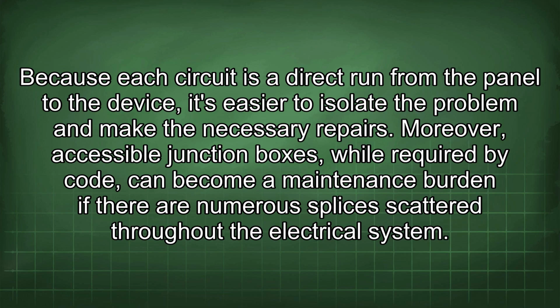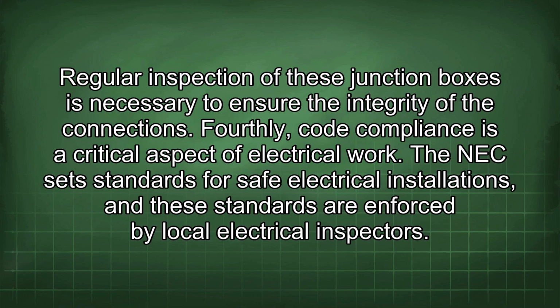Moreover, accessible junction boxes, while required by code, can become a maintenance burden if there are numerous splices scattered throughout the electrical system. Regular inspection of these junction boxes is necessary to ensure the integrity of the connections. Fourthly, code compliance is a critical aspect of electrical work. The NEC sets standards for safe electrical installations, and these standards are enforced by local electrical inspectors.